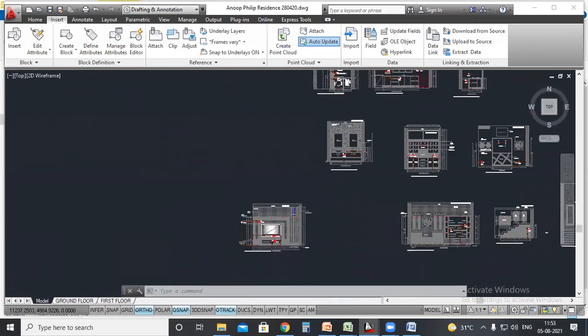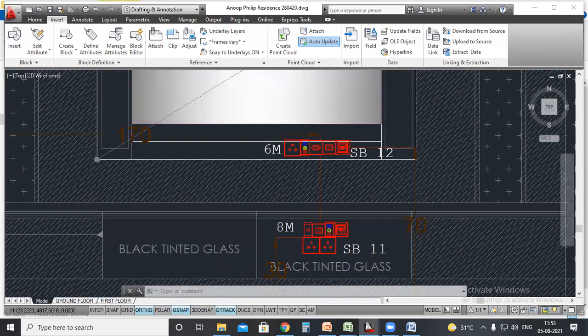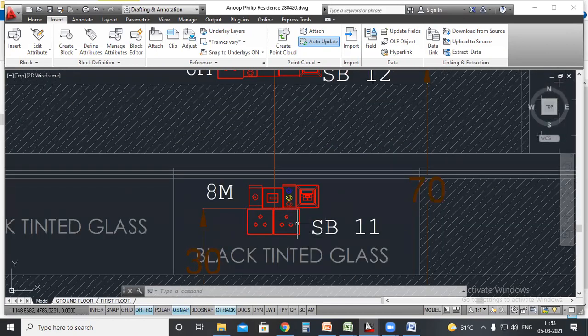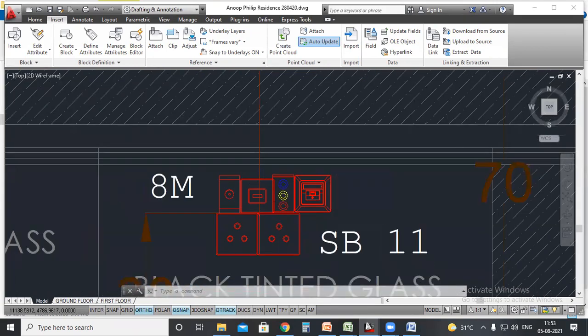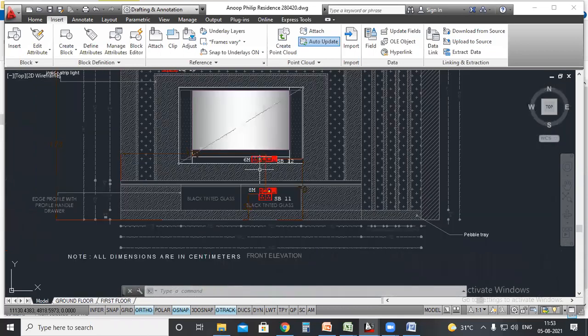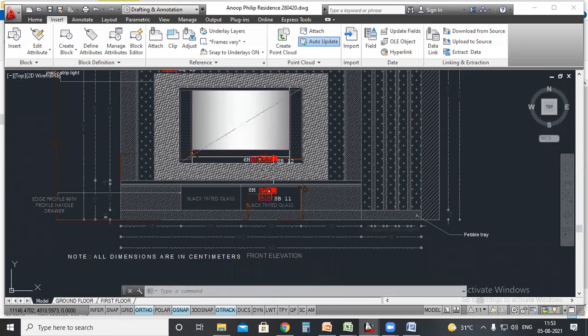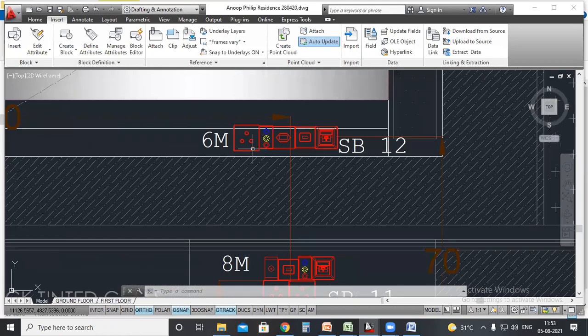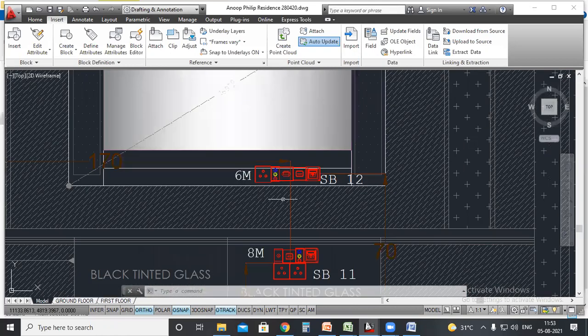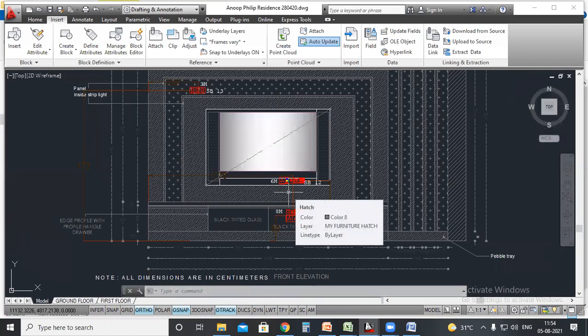Yeah. If you see the elevation area for the television part, you can see we have arranged sockets and TV audio video point, coaxial point here and also here. Because when we saw that particular 3D image, we could understand that it would need a separate height. Always you have to think that way, because the set-top box or the TV receiver will have a separate height. Then the TV point will also need a socket. So if you provide all three sockets at a particular point, the wires will be visible, because the client had an important requirement that no wires should be visible.